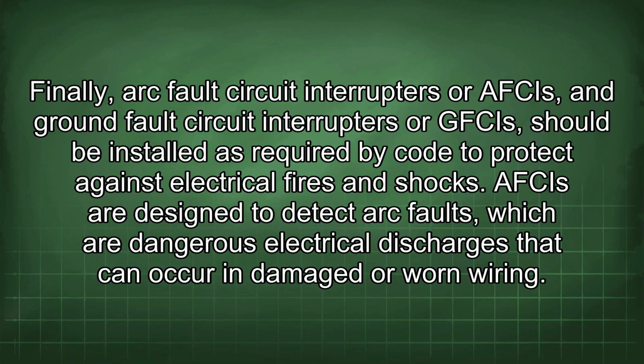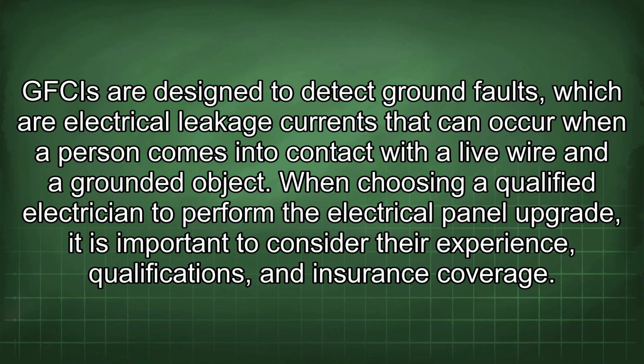AFCIs are designed to detect arc faults, which are dangerous electrical discharges that can occur in damaged or worn wiring. GFCIs are designed to detect ground faults, which are electrical leakage currents that can occur when a person comes into contact with a live wire and a grounded object.